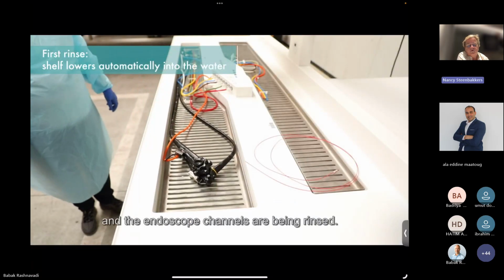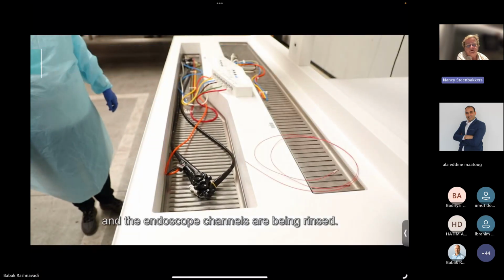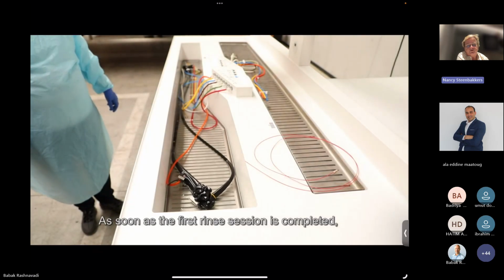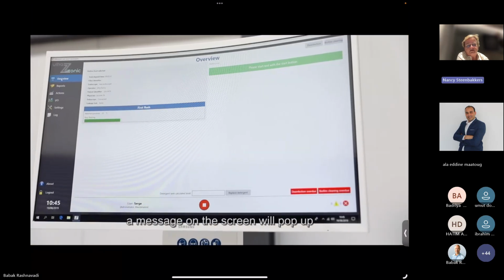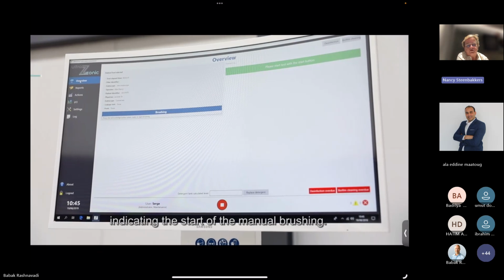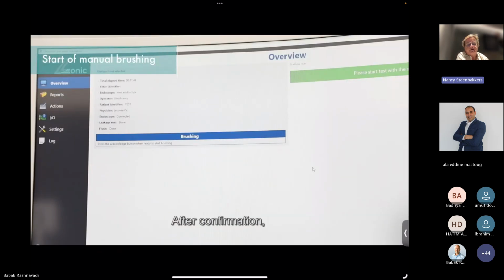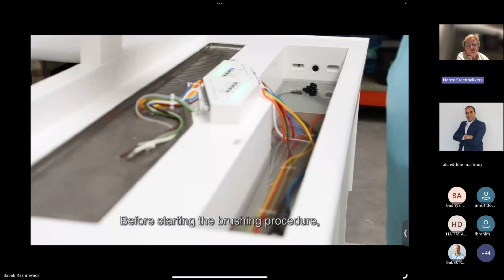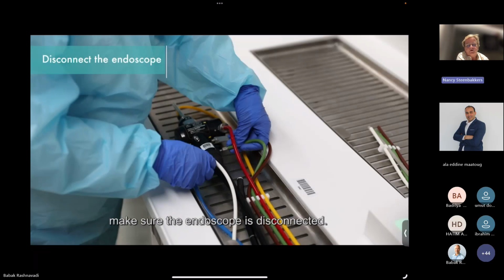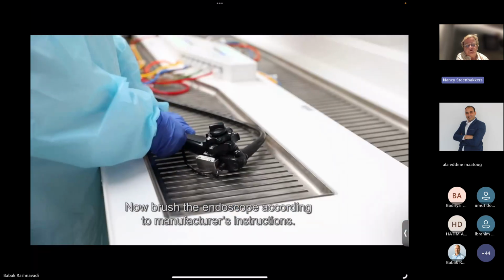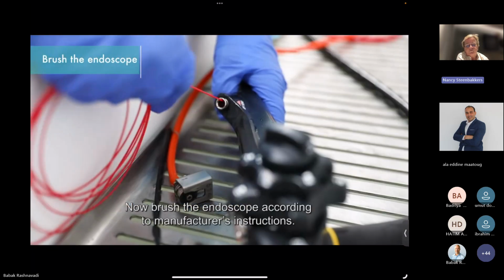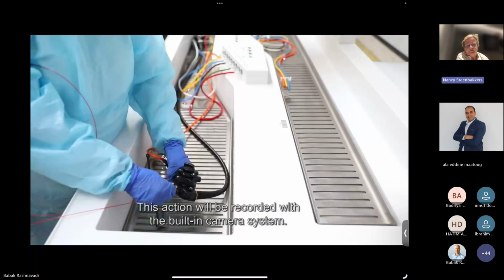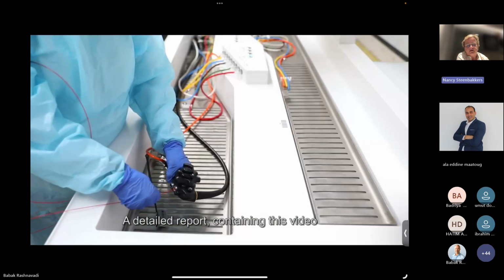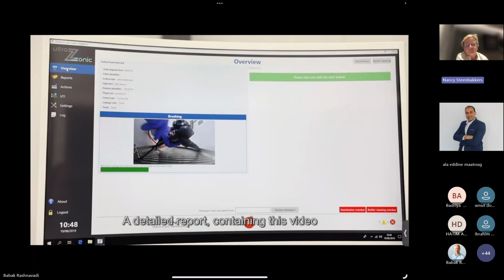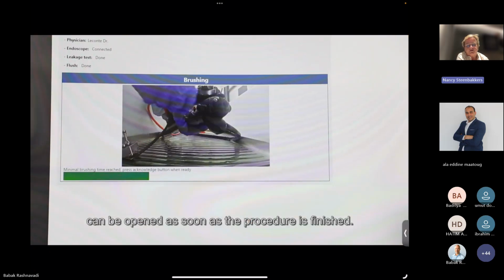So here you can see the lower part going down in the water, because during the leak test the sink was filling up with water and detergent. Here you can see on the screen that we are doing the flush, and all the steps that we've already done are also shown on the screen. So for brushing, you just click on that button, it goes up, and there in front of the camera the endoscope will be brushed. This is the image you can also see on the screen, the image you see while you're performing the brush cycle.